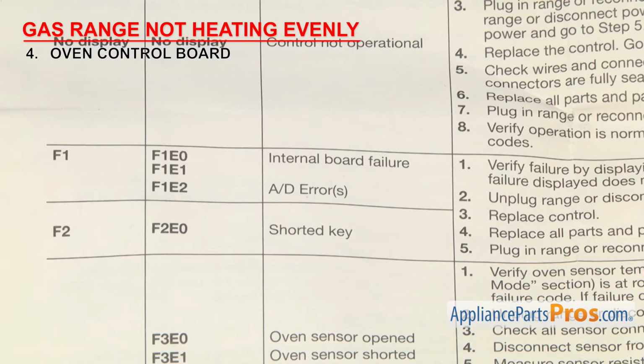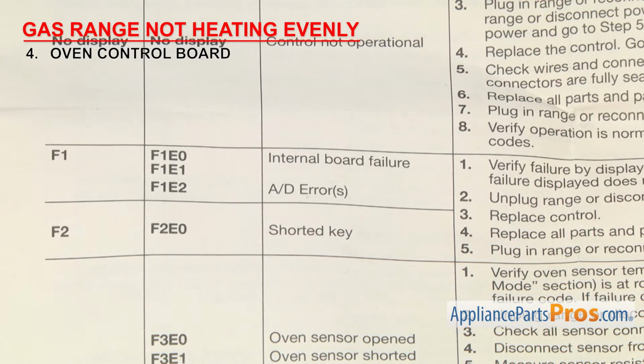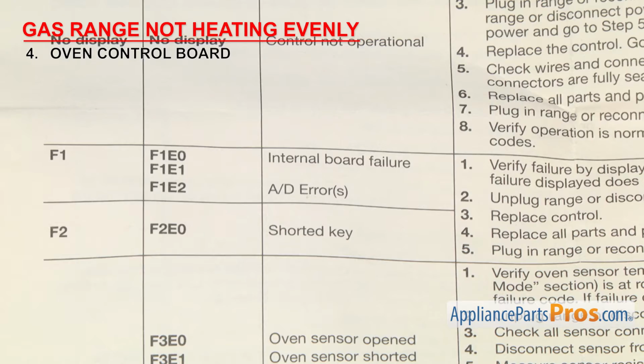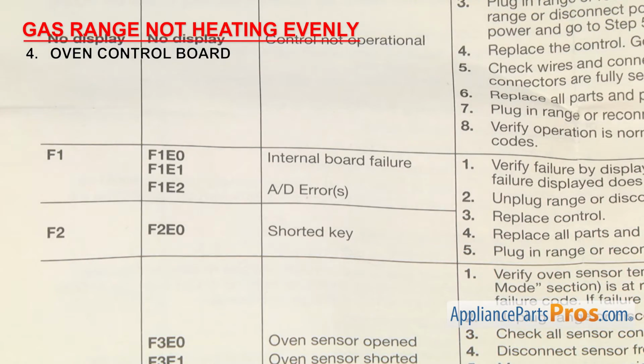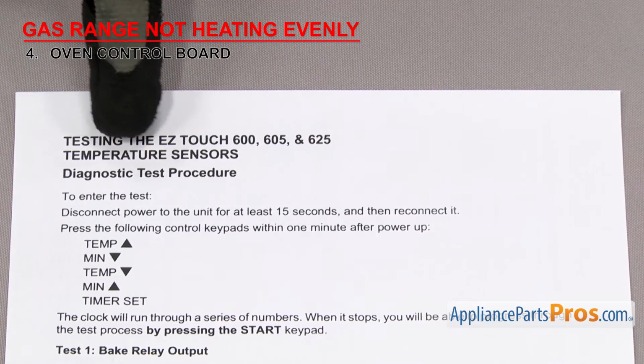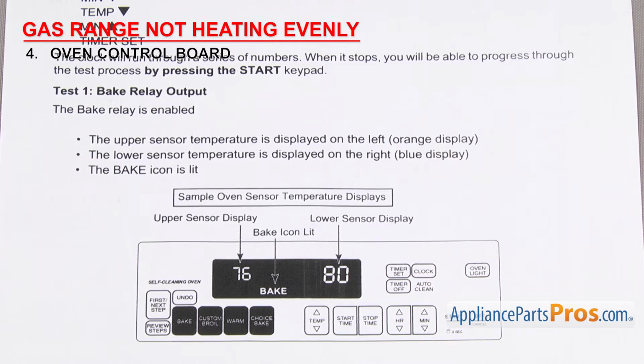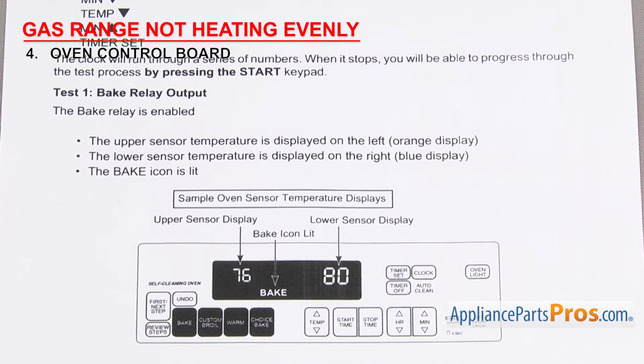There are a lot of different control boards out there, so we can't show you how to test them all. You're going to have to grab your tech sheet and follow the diagnostics or error codes to see if it's gone bad. In this example, you'd have to enter the diagnostic mode and test the bake relay to make sure it's sending power to the igniter. If it fails the test, you'll have to replace it.